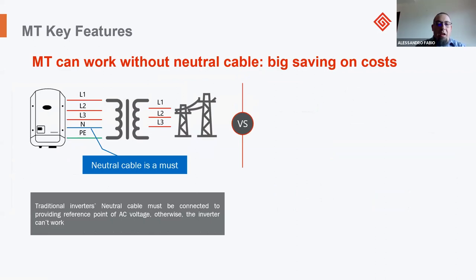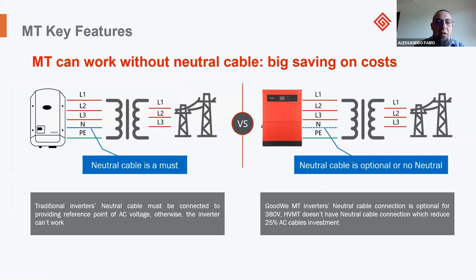So we also have the possibility for the connection. For example, with some competitors, a neutral cable is a must because the technology needs the neutral cable. But in our case, we can put it or not, so we can use our inverter in a star or delta connection for the primary transformer without any problem. So it's optional. You can put it on site if you need it directly, with a simple connection, without any specific setting.